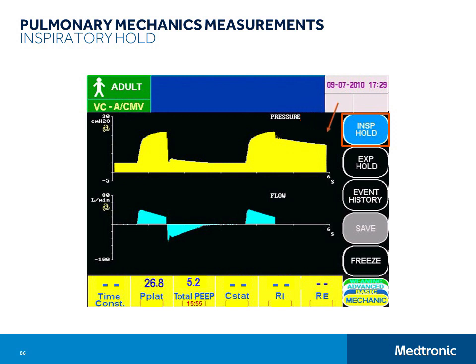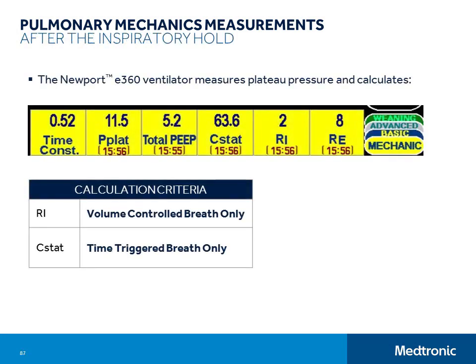When an inspiratory hold is performed, the e360 measures the plateau pressure, then performs mathematical calculations for resistance and compliance. Inspiratory resistance is only calculated if the breath was a mandatory volume control breath with a square flow waveform, and static compliance is only calculated if the breath was a time-triggered breath rather than being triggered by the patient. Because you already performed the end expiratory hold, the C-stat measurement will be based on total PEEP.